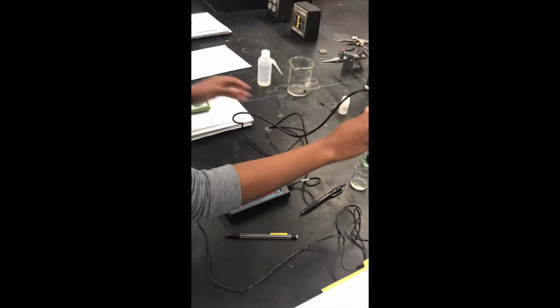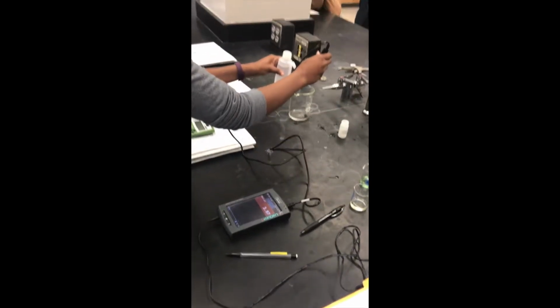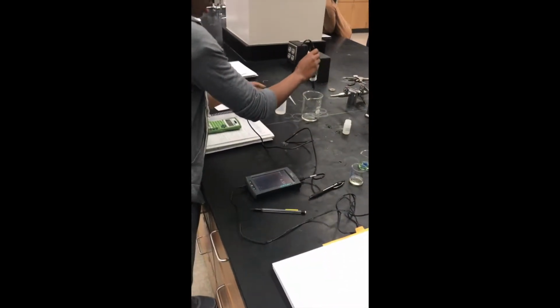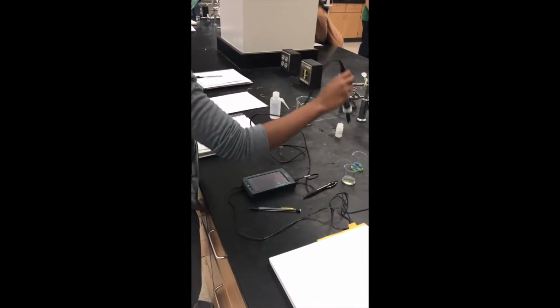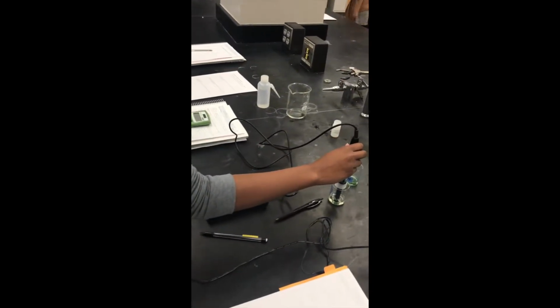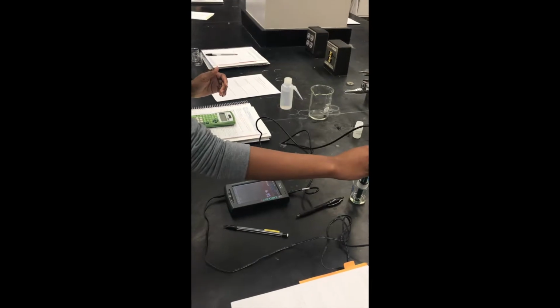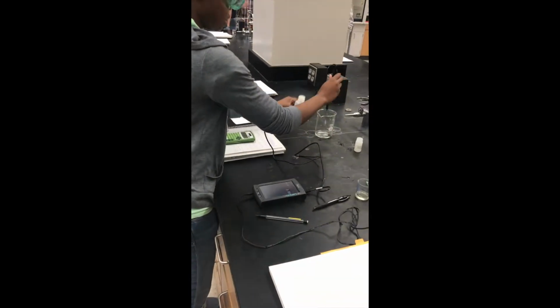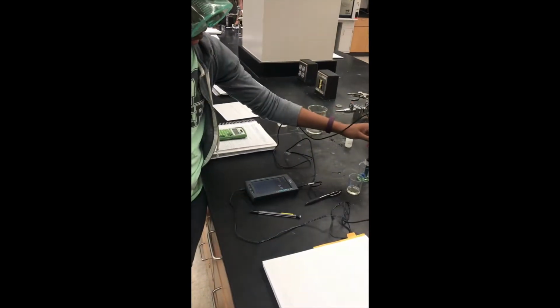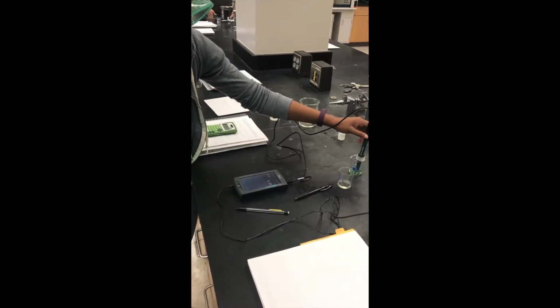and then tested each solution to make sure our pH meter accurately read each pH solution. If it does not accurately read the pH buffer solution, that means that you didn't do the calibration right and you're going to have to do it over again. If it did, that means you're good to go and that you're going to be able to test the solutions accurately.